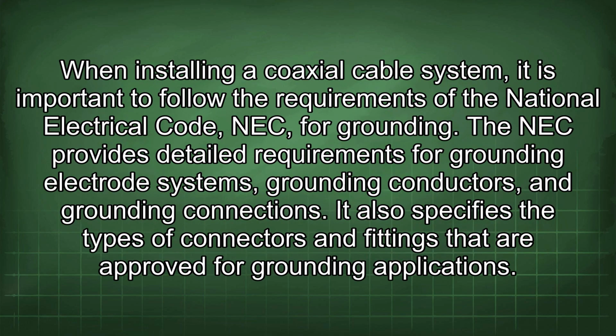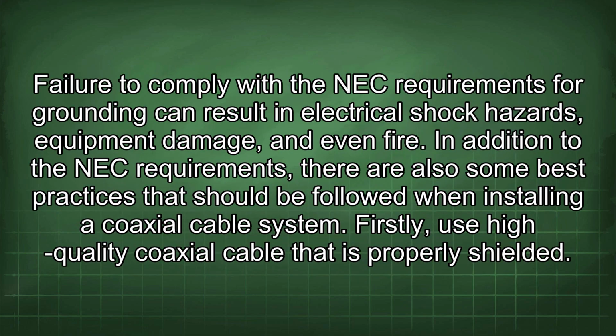When installing a coaxial cable system, it is important to follow the requirements of the National Electrical Code (NEC) for grounding. The NEC provides detailed requirements for grounding electrode systems, grounding conductors, and grounding connections. It also specifies the types of connectors and fittings that are approved for grounding applications. Failure to comply with the NEC requirements for grounding can result in electrical shock hazards, equipment damage, and even fire.